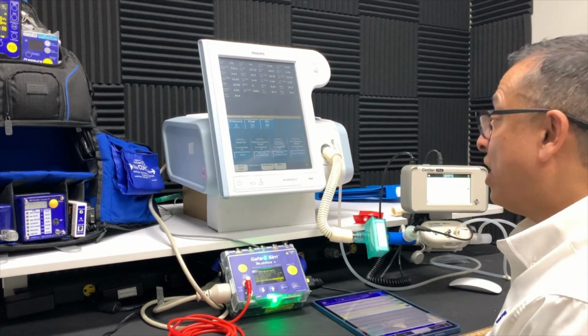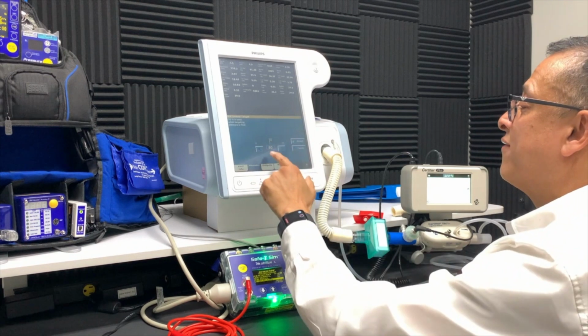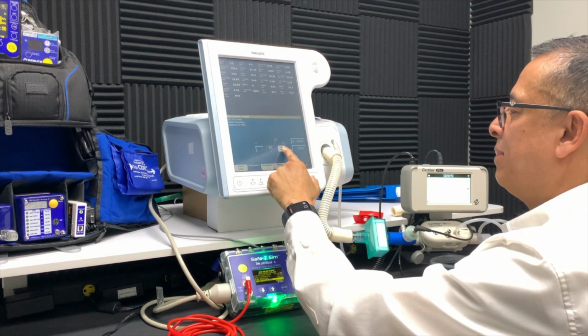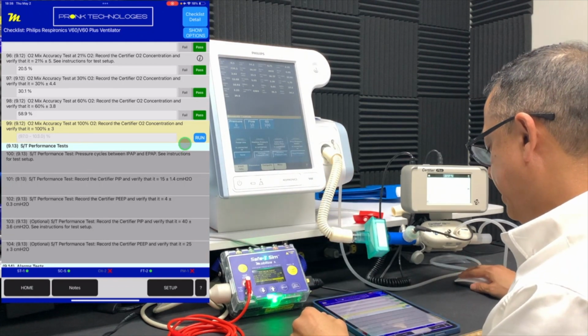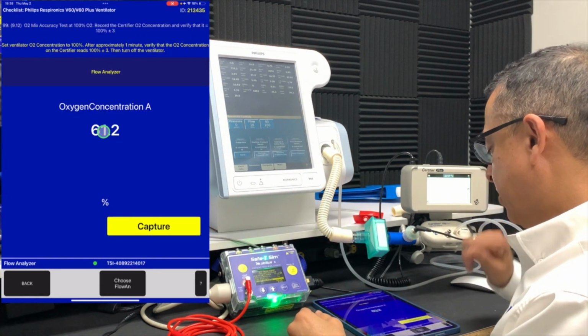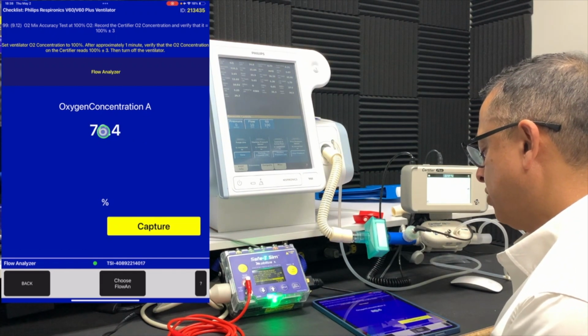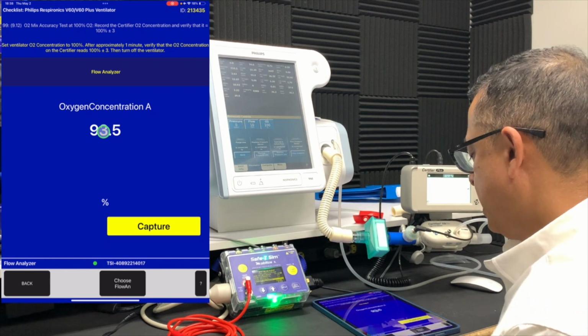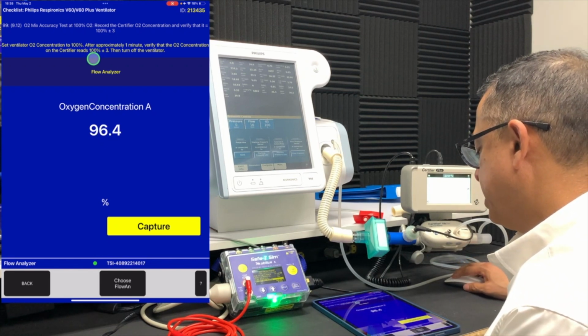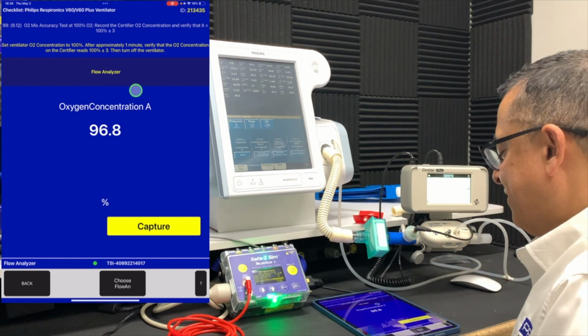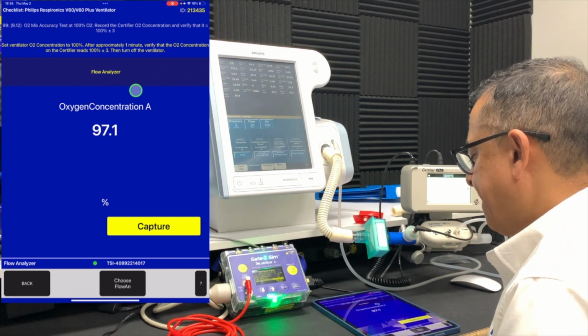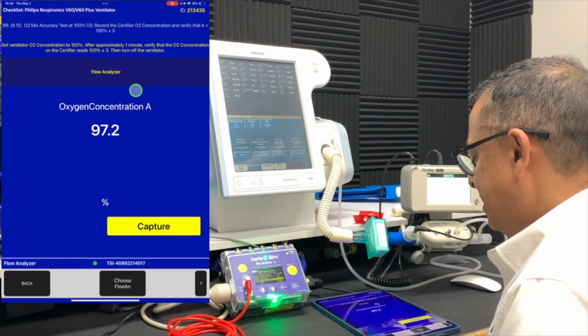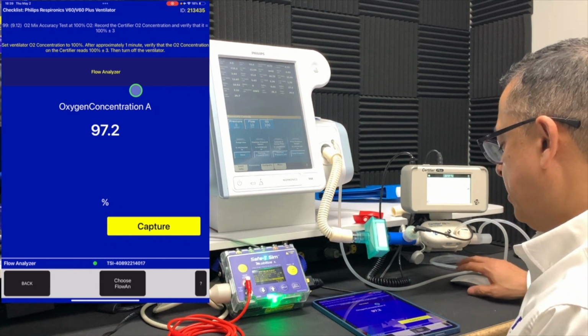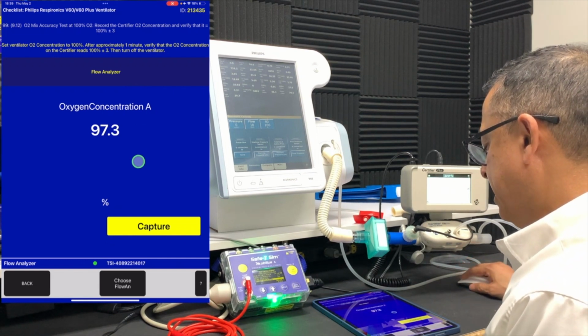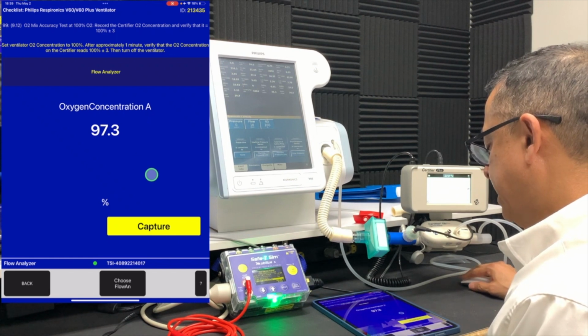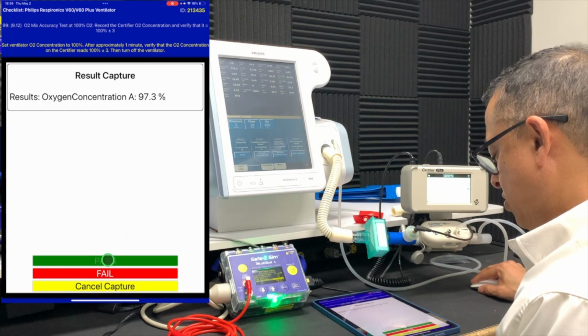So our next test is to do it at 100%. So we'll go ahead and set the ventilator for that, and to make sure that we're doing and passing that test. So we'll go ahead and do that. We'll go ahead and make the measurement. Just like the others, it takes a moment for it to ramp up its output to 100%, but we want to make sure we get to 100% plus or minus 3. So we need to get over 97 and make sure that it's within that limit. And so we'll wait for it to stabilize. You can see here we're on the lower end, but we are within the pass-fail limits within the procedure. So we'll wait for that to stabilize, make sure it stays consistent. And it looks like it is. So we'll capture that result, pass it, go on to the next test.